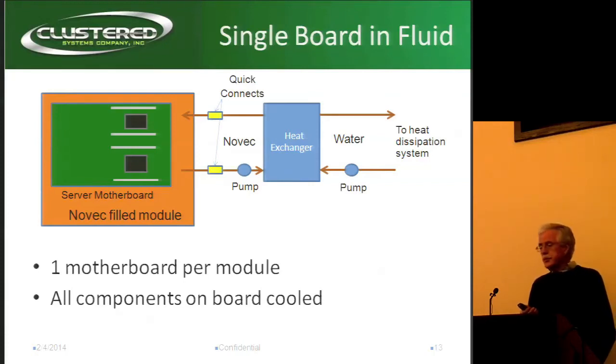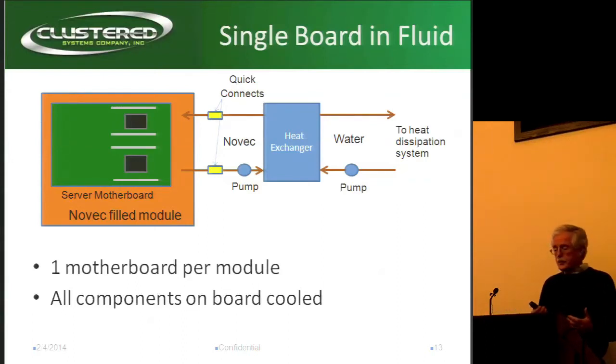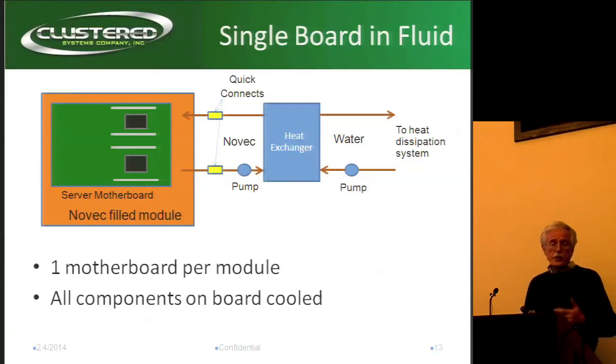For single-board immersion, there are actually two ways this is done. One is by a company called LiquiCool and the other is a slightly different method by Iceotope. In these cases, they fill the module with fluid and the motherboard sits in the fluid. One potential issue is it hasn't been proven how much the Novec can dissolve the varnishes on the board — maybe it's not a problem at all. But the good thing is that all components on the board are cooled, just like Green Revolution, so you don't have any piecewise cooling. But you've still got the Quick Connect.